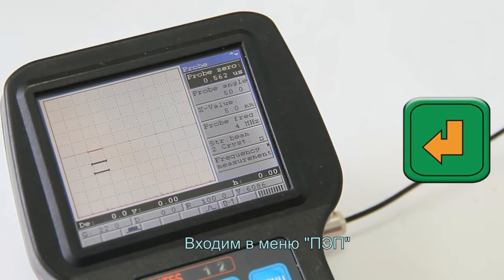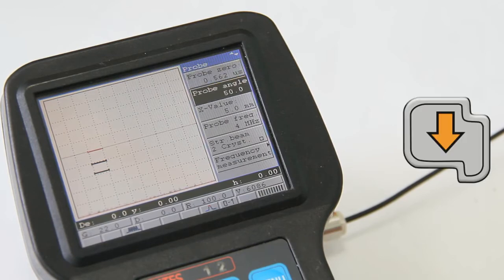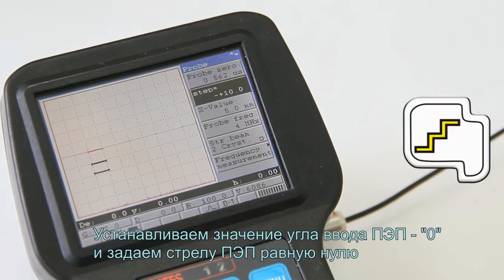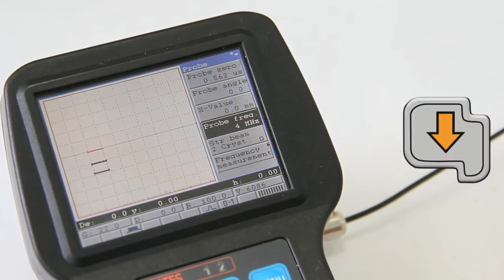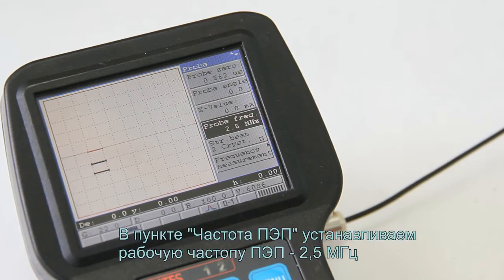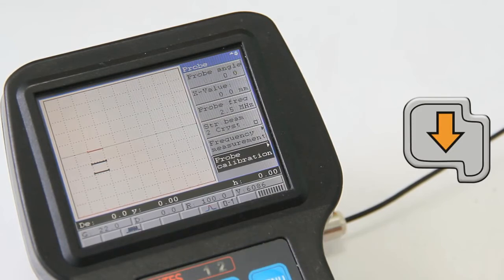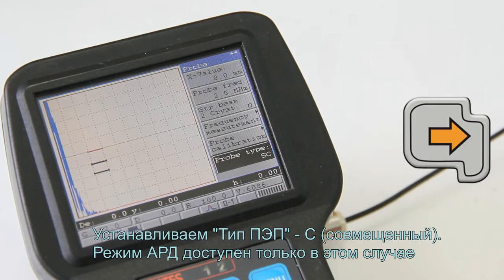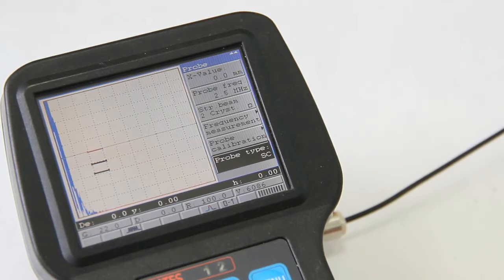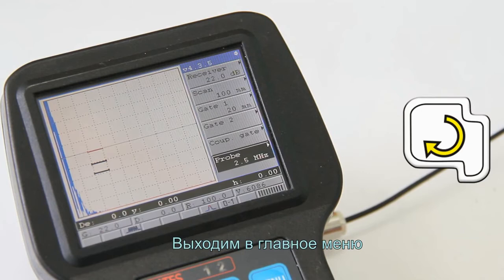Enter the probe menu. Set up the probe angle value to 0 and set the X value that equals 0. In probe frequency item, set up the probe operating frequency to 2.5 MHz. Set up the probe type item, single crystal. The DGS mode is available in this case only. Return to the main menu.